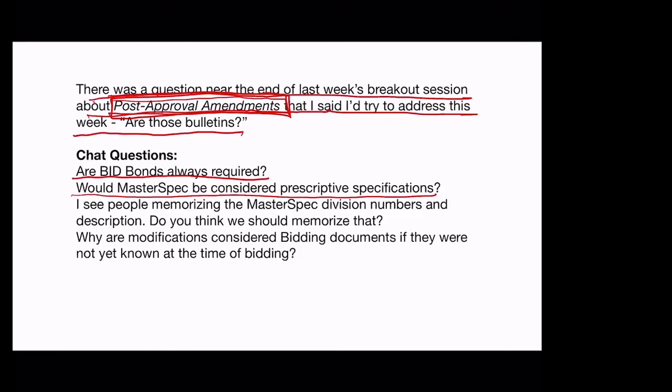And those specs could be prescriptive, they could be performance, they could be proprietary, and likely they're combinations of all three. Even within the same spec, it may have a description about how it performs. It needs to provide continuous power at 277 volts. It needs to be made with a fluid that cools it down, that is fire resistant, and so forth. So it may talk about how it performs. It may be prescriptive in that it actually explains to the contractor how she's going to put it on a pad. You will first put it on a pad that will be made of this. And it could be proprietary in that it actually calls out a specific manufacturer and model number.